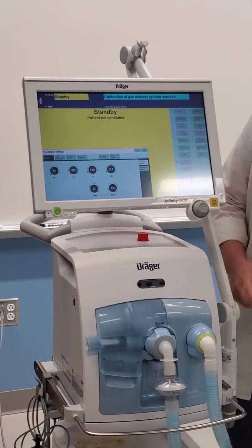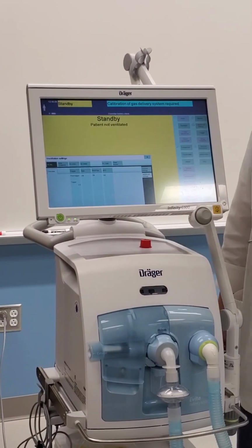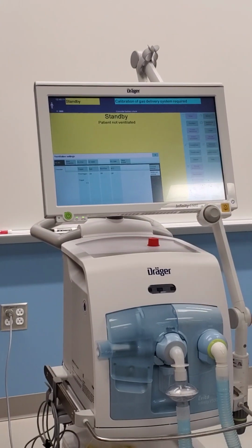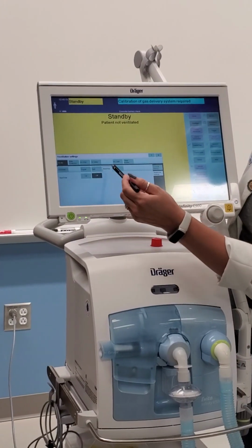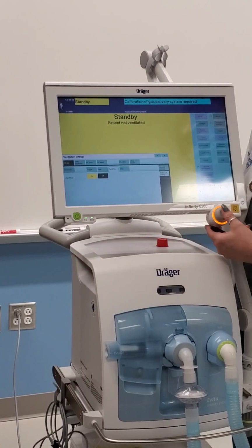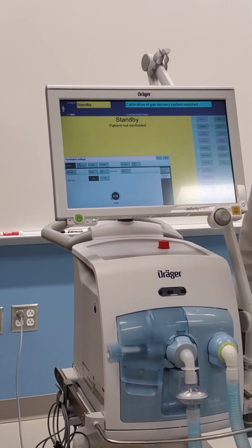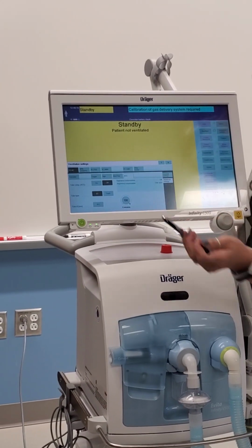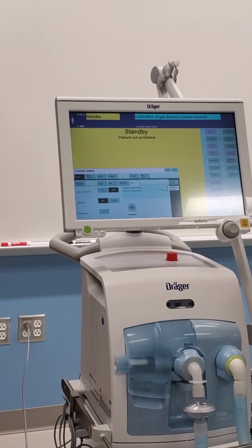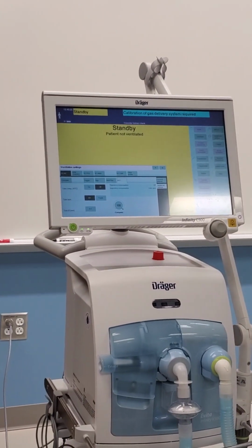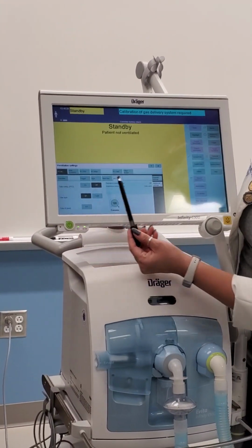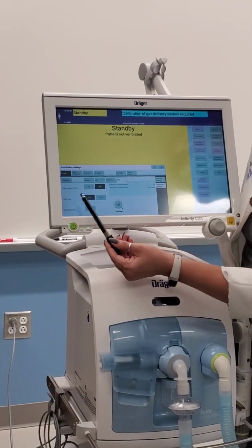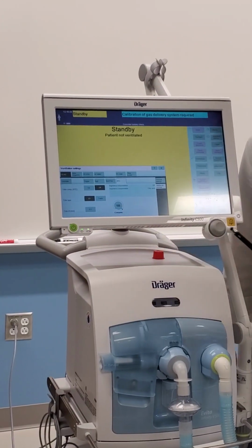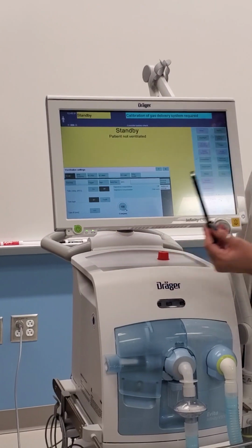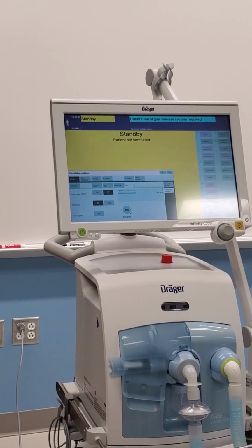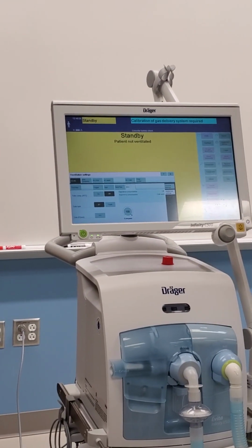So I always advocate for turning your auto flow on. You do that in additional settings, and you'll find auto flow on. Boom, we're good to go. You have automatic tubing compensation. Remember we talked about that? You put in the tube if you want it on or off. Is it an ET tube or a trach? What size is it? How much compensation do you want, the percentage? It's all right there.